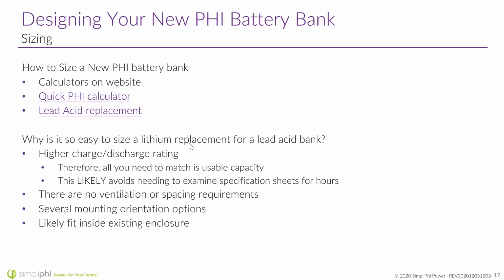It really is easy to size a lithium replacement for a lead acid bank. You have a higher charge and discharge rating with lithium than with lead acid, so if you simply match the usable capacity, you'll always be able to power the same amount of loads or more at any one time. For example, say you have a 400 amp hour lead acid battery bank, but you're only using 20% depth of discharge—that's effectively an 80 amp hour battery. Our SimpliPhi batteries are 75 amp hours each, so only one to two batteries would be needed in that scenario. This helps you and your installer avoid examining spec sheets for hours.